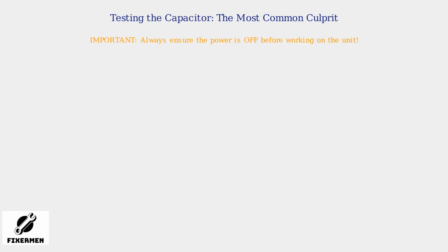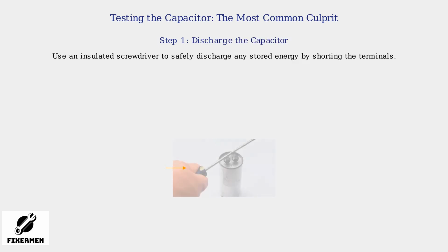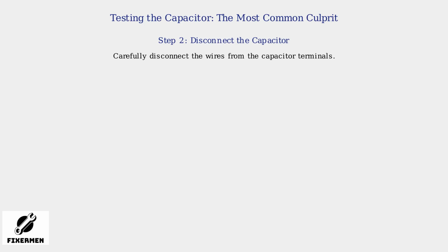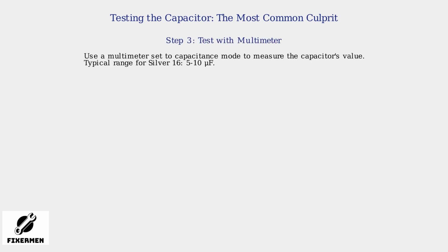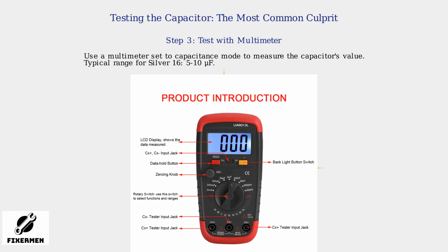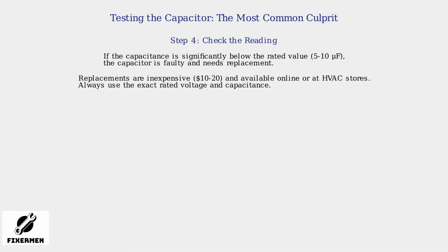Before testing the capacitor, always ensure the power is completely off to avoid electrical shock. First, discharge the capacitor to release any stored electrical energy. Use an insulated screwdriver and carefully short the two terminals together for a few seconds. Next, disconnect the capacitor from the circuit by removing the wires attached to its terminals. Now, use a digital multimeter with capacitance testing capability. Set it to capacitance mode and connect the leads to the capacitor terminals. The display should show a reading in microfarads. Check the multimeter reading. For the Silver 16, the capacitor should typically measure between 5 and 10 microfarads. If the reading is much lower than this rated value, the capacitor has failed and needs to be replaced.